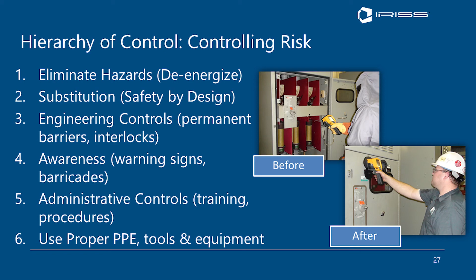So 70E's got some interesting language in it about infrared inspections. It basically says you can do infrared or ultrasound condition-based type inspections without the need for PPE, but not if you open the door of the panel. As soon as you open the door of the panel or you remove a cover of the panel, everybody's got to be in PPE. So it's got some very specific language about that baked into the 70E as well.